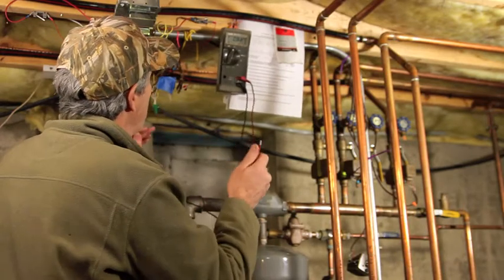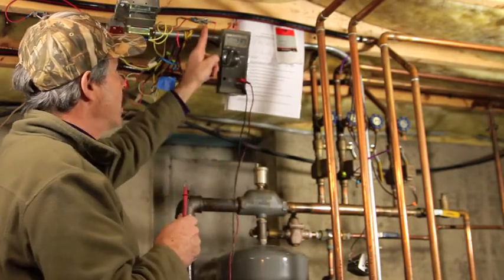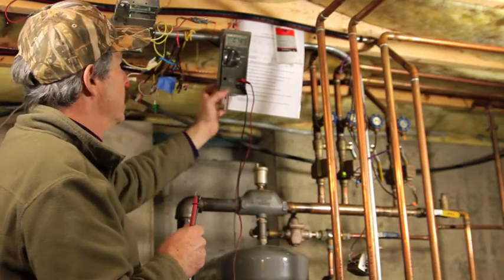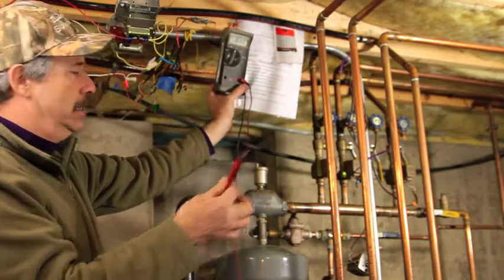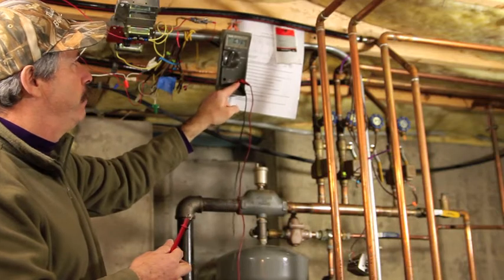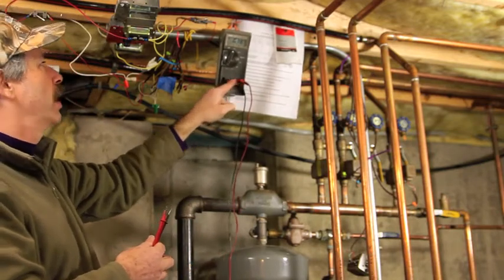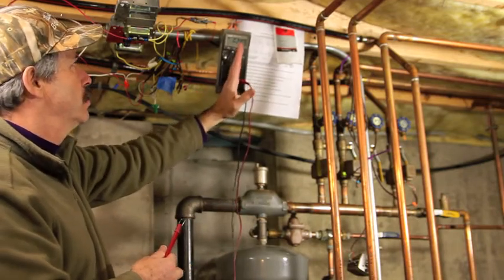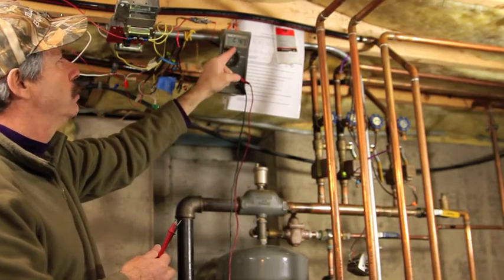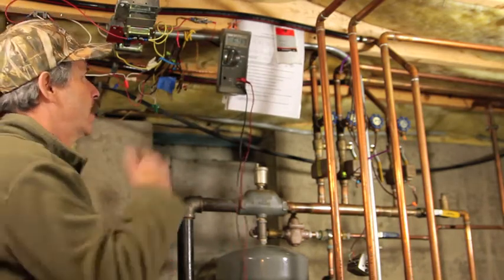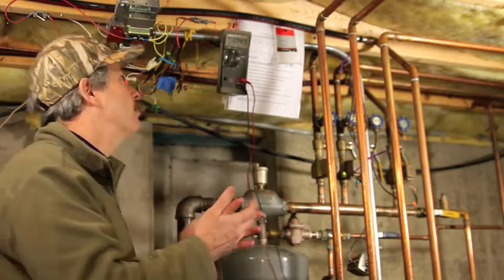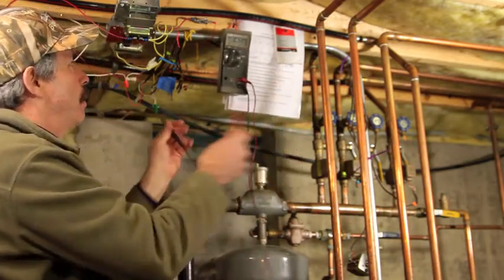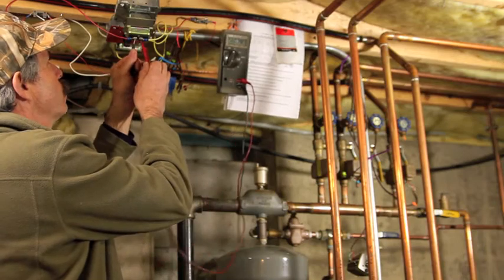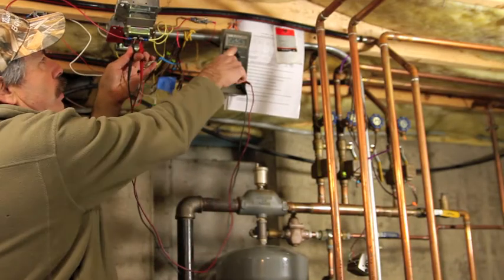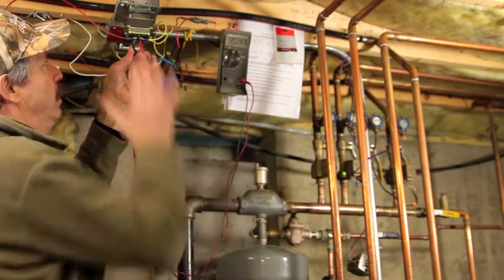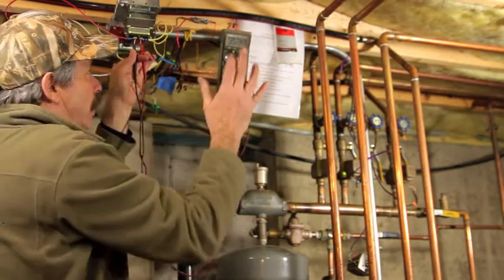Okay. So what you do to check this fuse with this system is you place your black lead in common, your red lead in the V port over here. Over here is the amperage. We're not using that method. You turn your dial to V with a squiggly line. That squiggly line means you're measuring an AC voltage. You then come over here and make sure your transformer works first off. Your transformer is giving you a good voltage. That way you know transformer works, your meter's set up correctly.